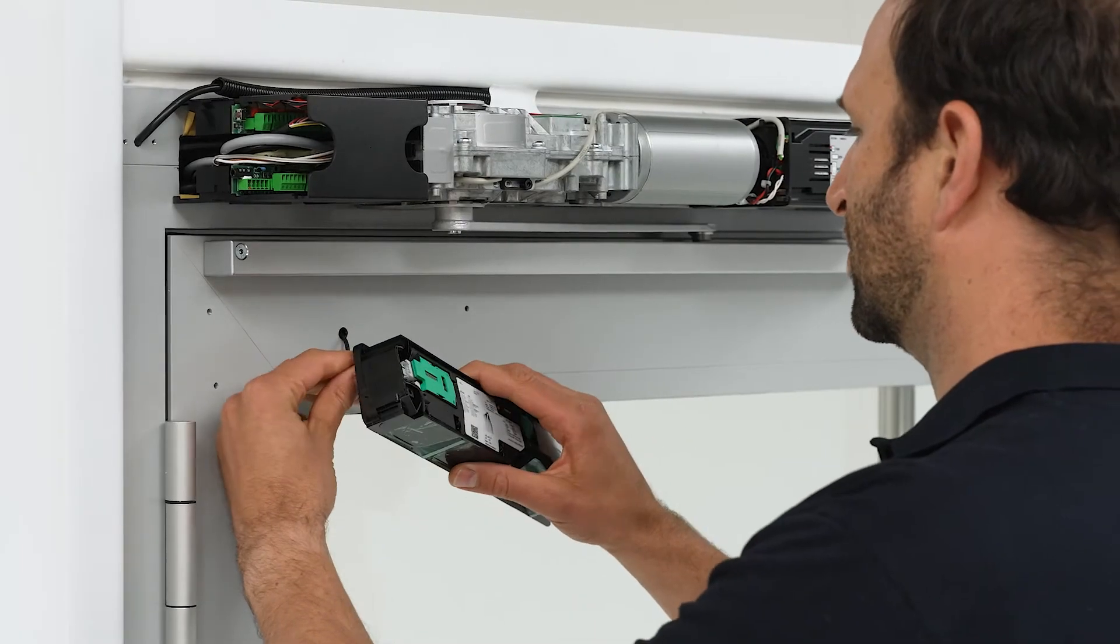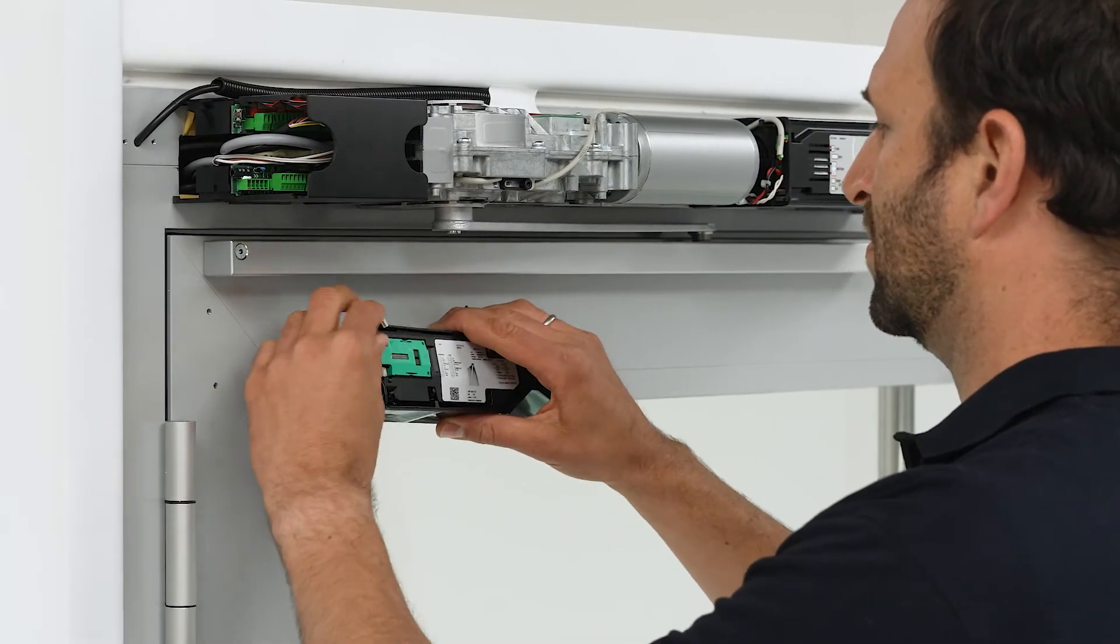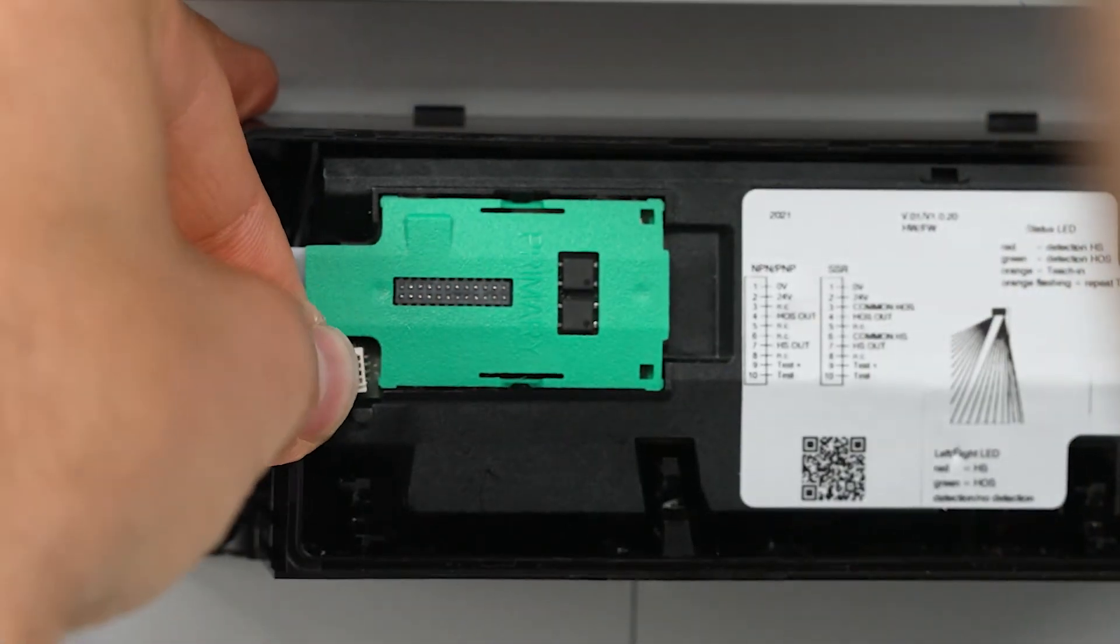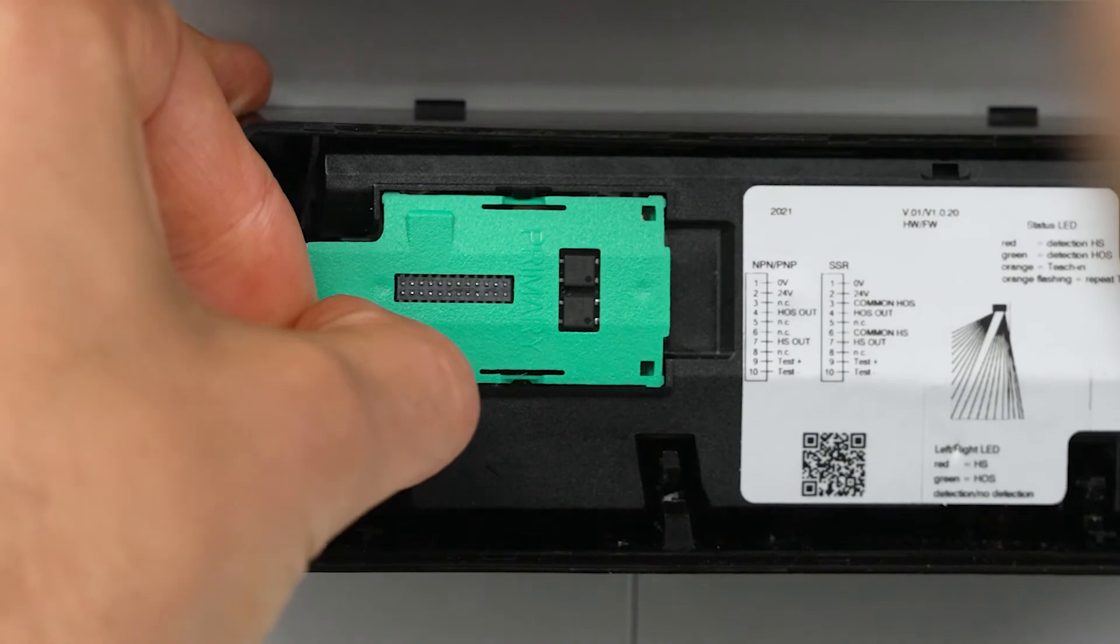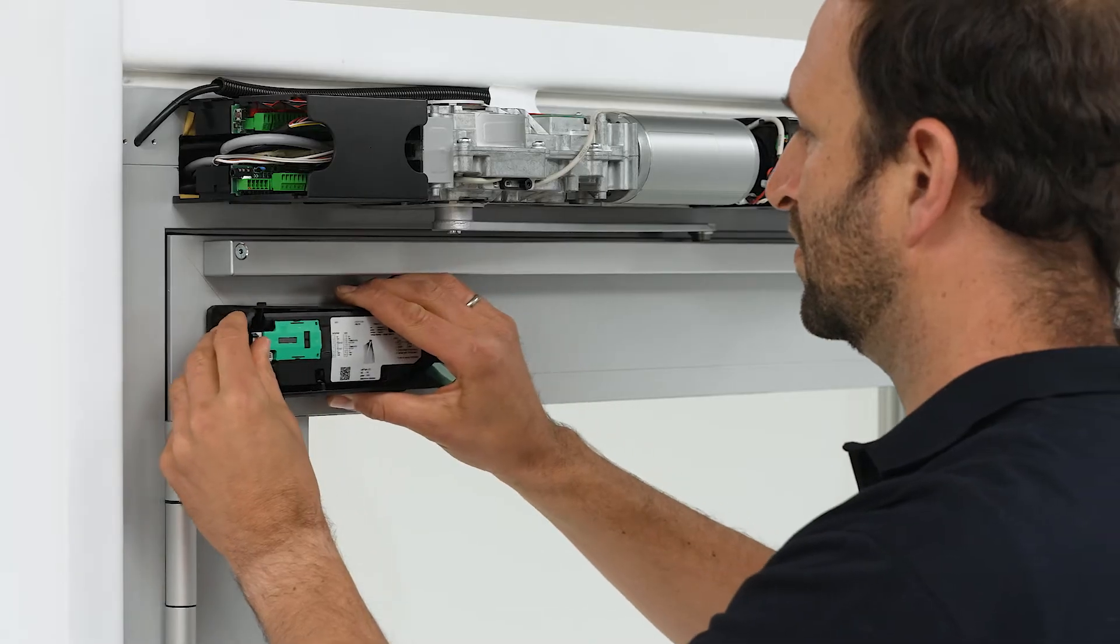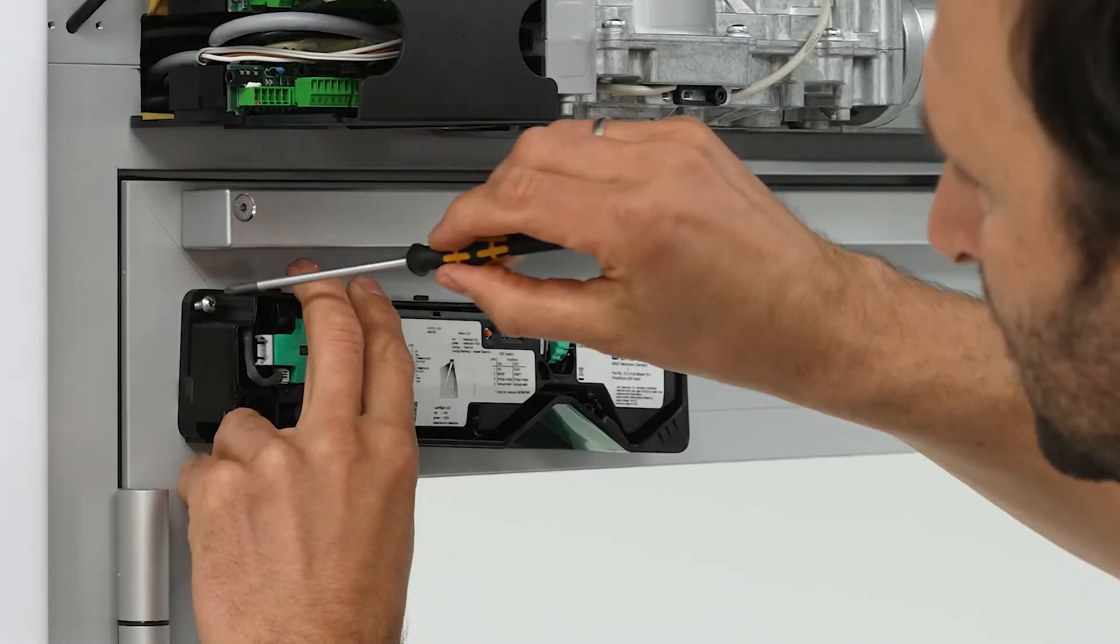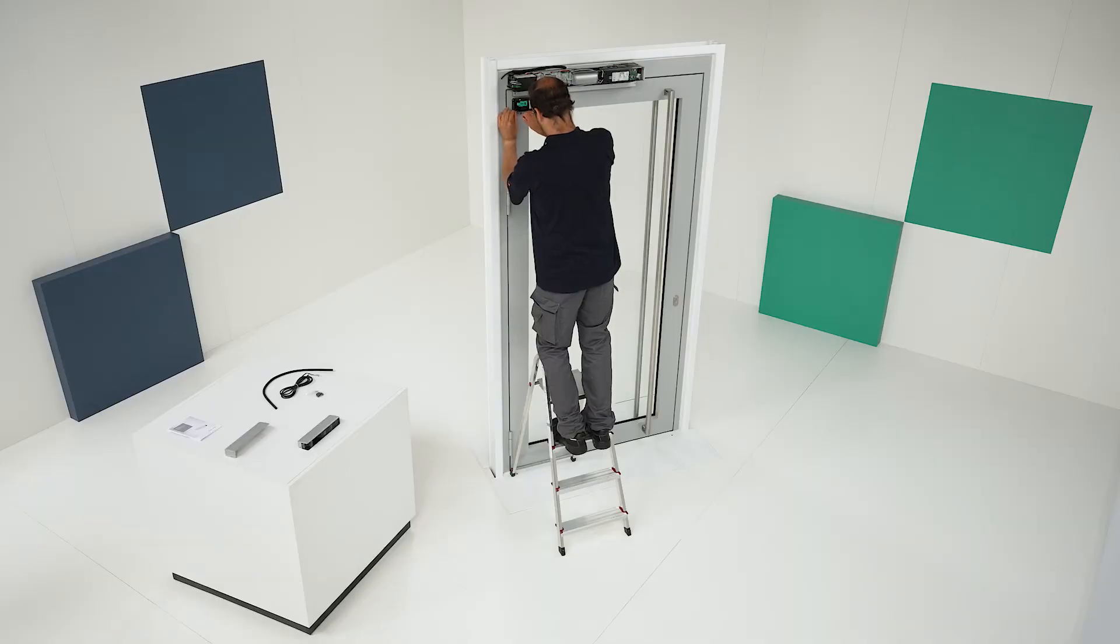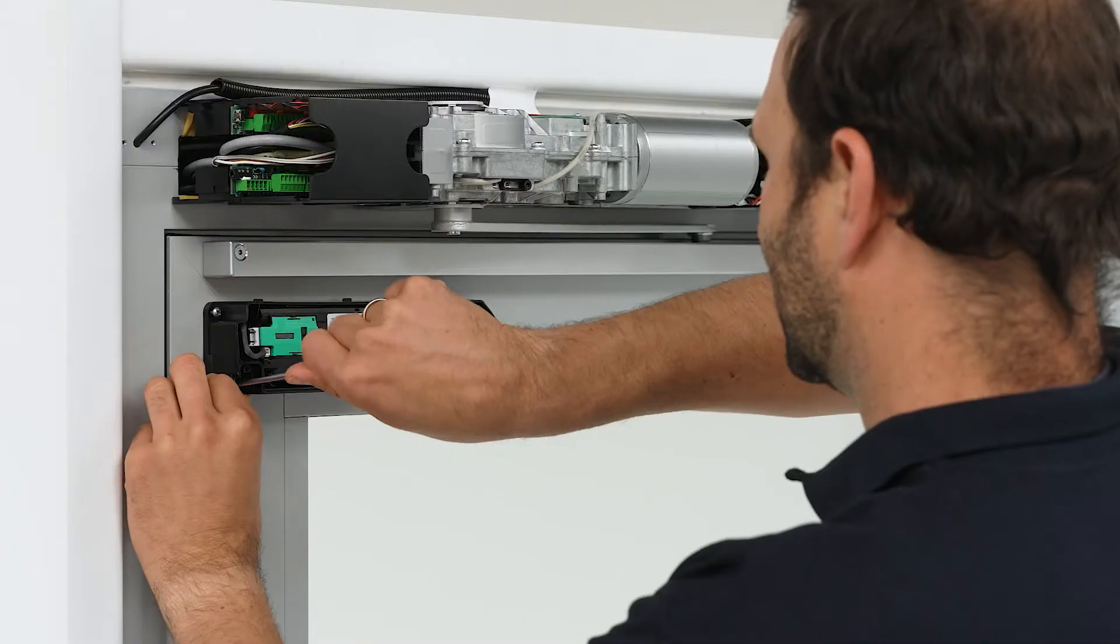Thread the door transition cable through the primary sensor. Leave approximately 50 mm of the cable hanging outside of the housing and plug the connector into the relevant socket. Then pull the rest of the cable through to the secondary sensor. Use a cross-head screwdriver and the supplied screws to secure the primary module in place. A third screw can also be used for added stability.